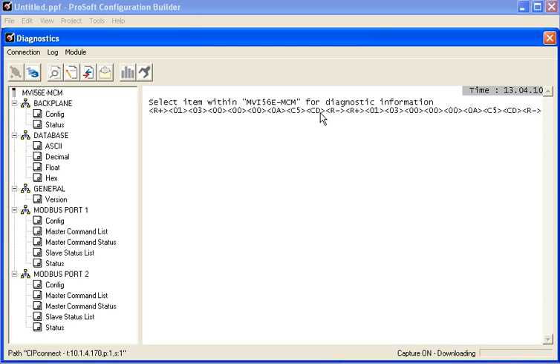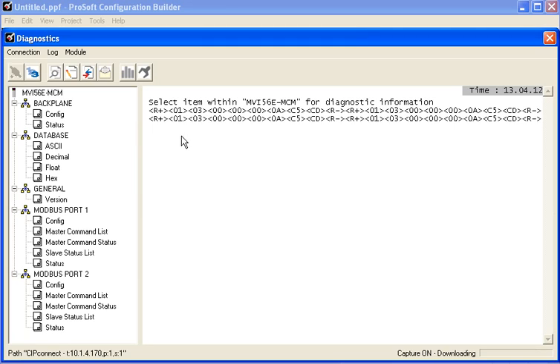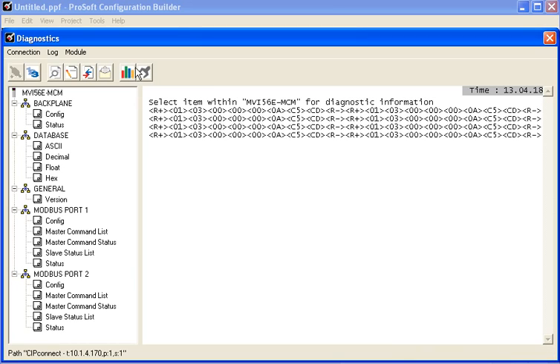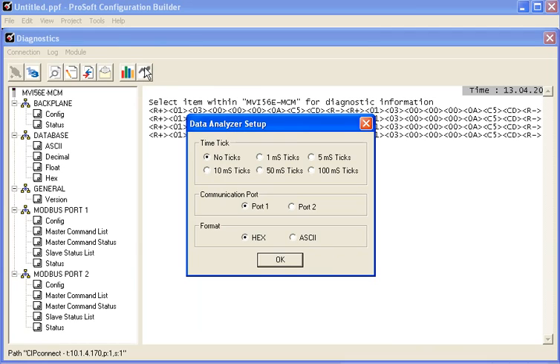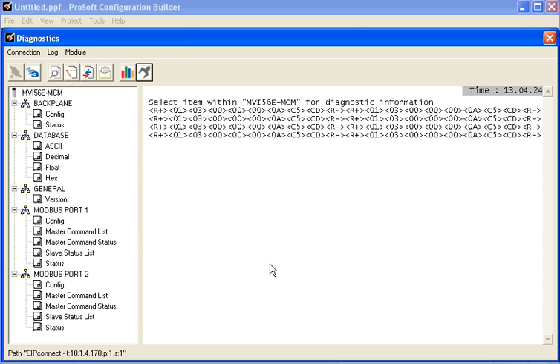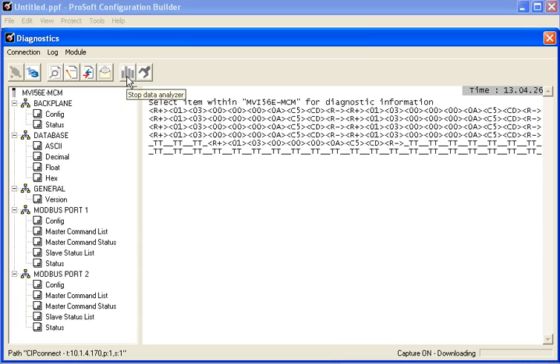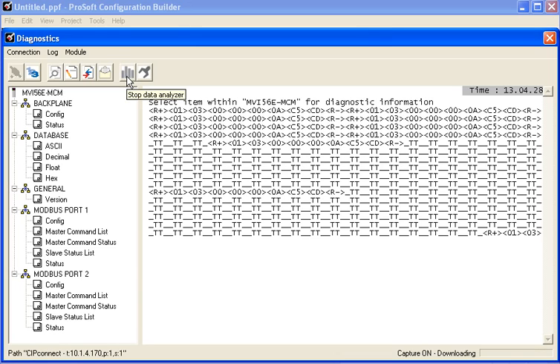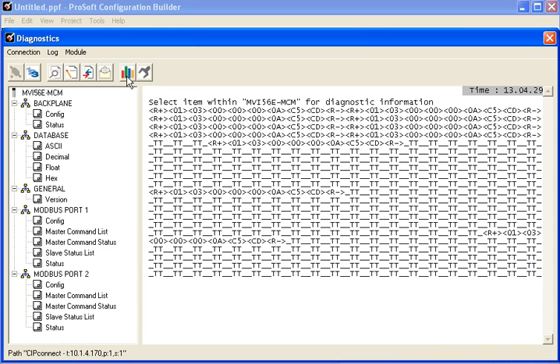So now it starts the data analyzer and now we can see that the module is generating traffic on our Modbus port number one. So I'll stop it. Now I'll click on the Setup button again and I'll show you the difference of what it looks like. So I'll click on 10 millisecond timing ticks. And now you see the difference here between what it looks like with timing ticks and what it looks like without timing ticks. This is extremely useful information when debugging a problem device on your Modbus network.